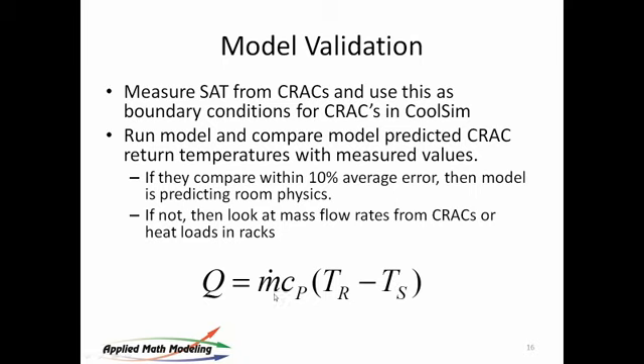The mass flow rate is being defined by the CRAC units themselves. The heat load is the IT equipment, so that's fixed. And the density of air is going to be the same. So the only thing that can be wrong is if the return temps don't match, then your mass flow rates are off. And that's common too for older units, because the filters get dirty, or something happens that degrades their performance. And so we've seen people doing measurements in the field tell us that in fact the rated mass flow rates are not always what they are, or the measured mass flow rates are not always what the published values are, depending on the age of the unit.